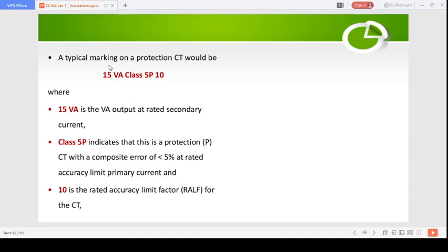Okay, so let's take a look at the typical marking on a protection CT. It would look something like that. Your protection CT would be marked something like this: 15 VA class 5P 10. Here 15 VA is the VA output at rated secondary current. So the VA output at the rated secondary current is the first part of this marking.